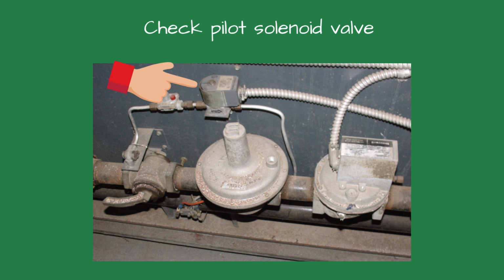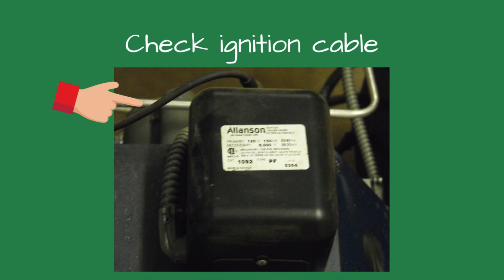Test the pilot solenoid valve. Verify the wiring is snug. Swap with a known good valve if available. Listen for the audible click when energized. Inspect the ignition cable. Look for cracks, burns, or loose boots. Ensure a tight fit at the transformer and electrode. Replace if insulation is brittle.